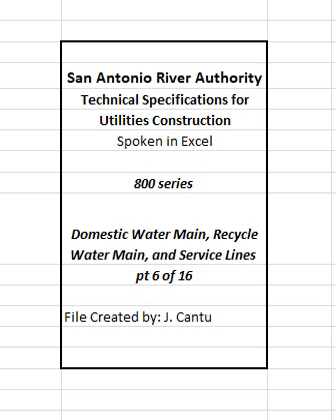Where new water mains and sanitary sewer mains parallel each other, they shall be at least 9 feet apart unless the sanitary sewer main is constructed of cast iron pipe or the equivalent of 150 psi pressure pipe with watertight joints, or unless other precautions approved by the Texas Commission on Environmental Quality, TCEQ, are taken to make the sewer main watertight and to prevent contamination of the water main.